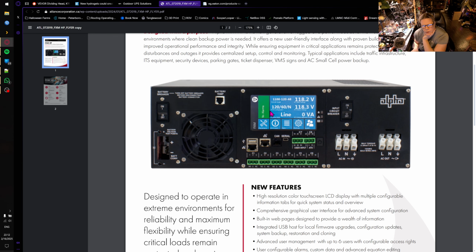So the point is that you should set your server so that when your batteries are nearly depleted, the server will shut itself down, okay? Now, what that's going to do is allow for a graceful shutdown of the server, which means that you're not going to have to worry about your databases being corrupted or any kind of damage to any of the software that's on there or loss of information, okay? This is going to save you so much bloody misery.